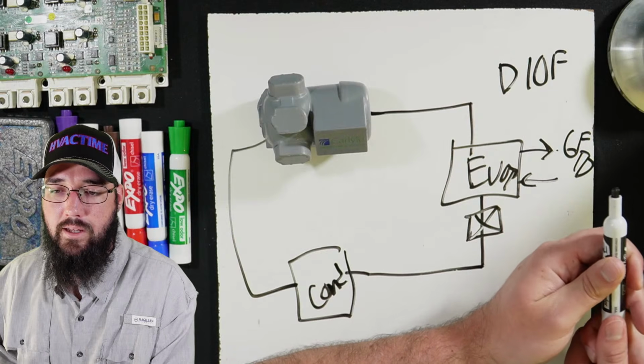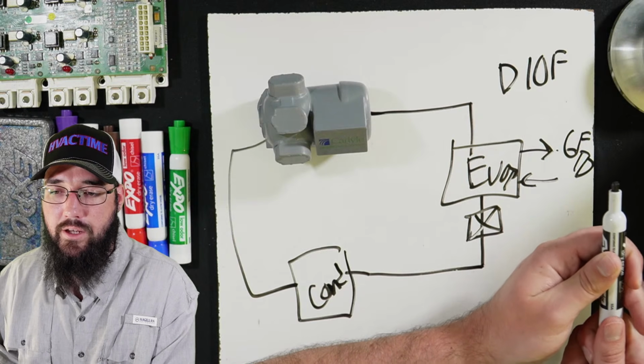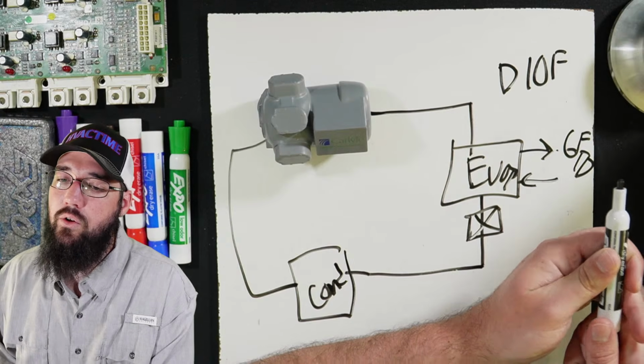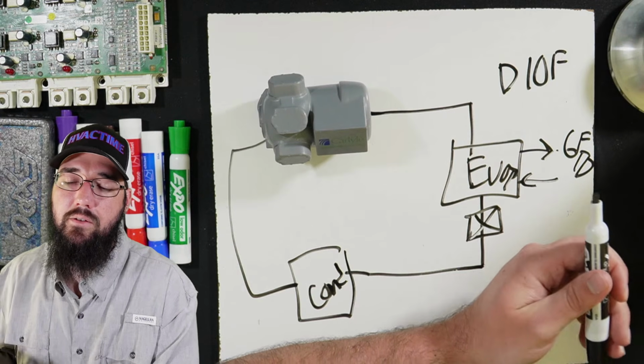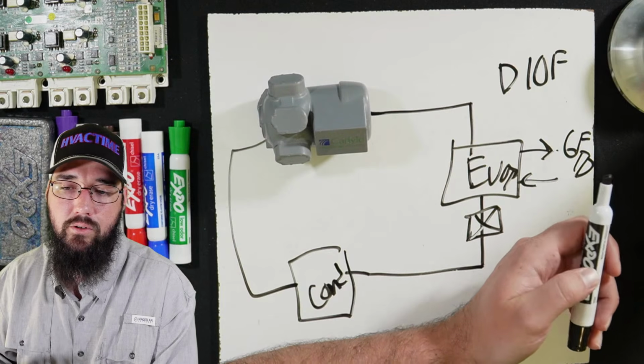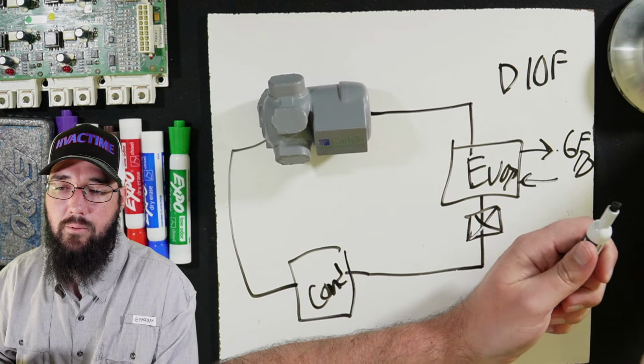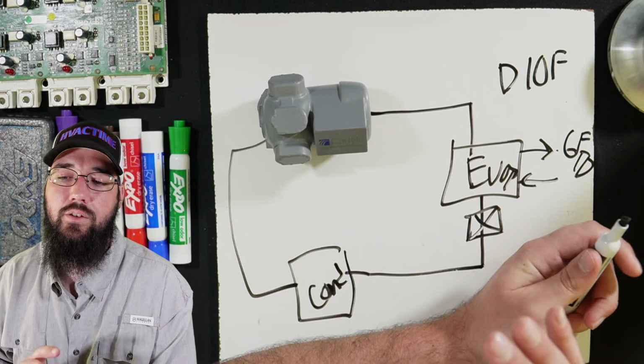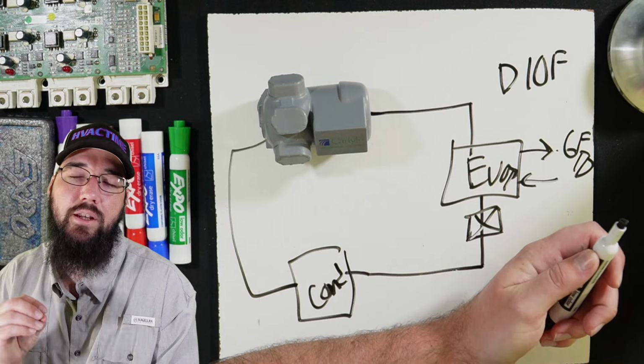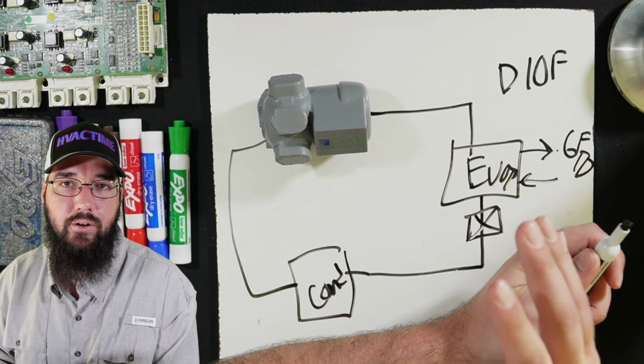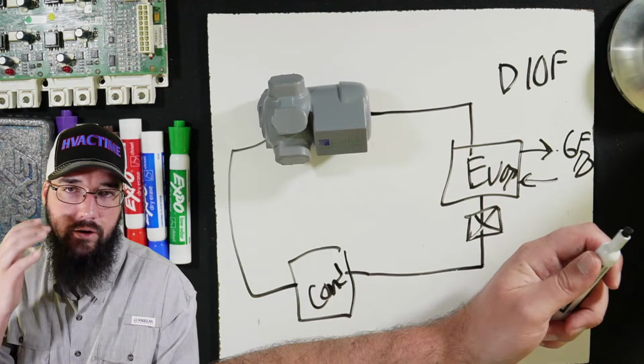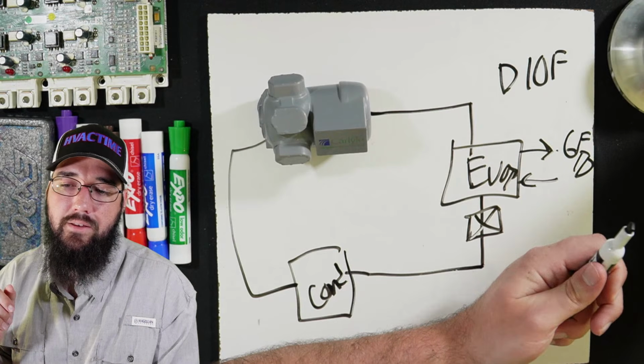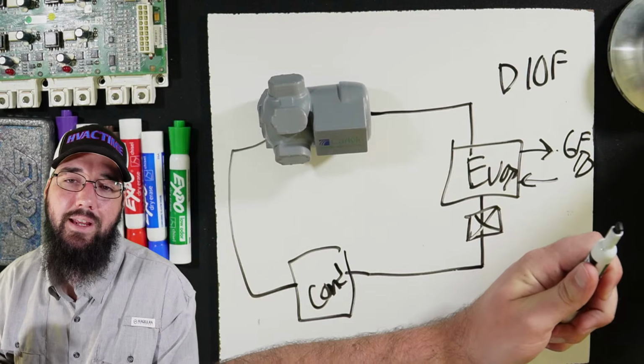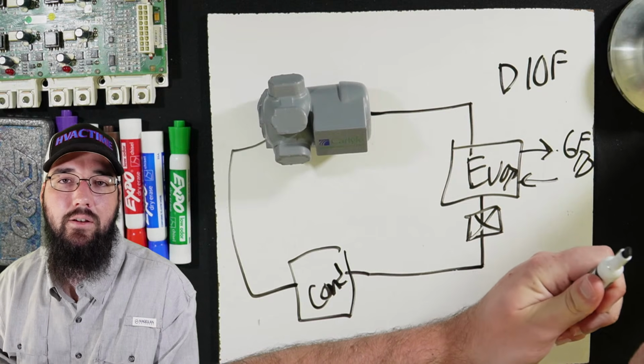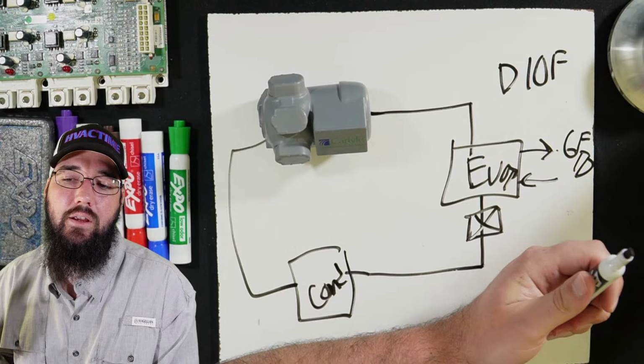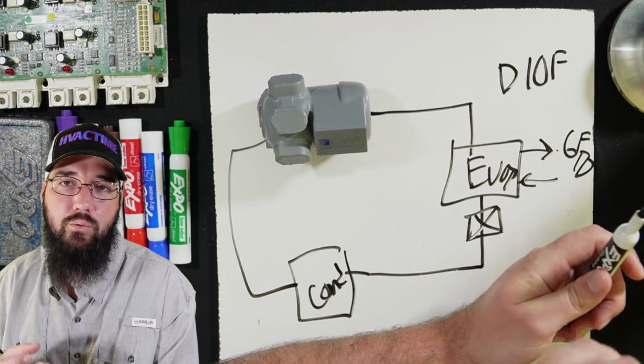So absolutely. Less CFM equals better heat exchange with water. So it's not about the refrigerant itself moving slower. It's not about the refrigerant moving slower, like we would think of it in an air-cooled scenario or an air-over evaporator, like an RTU. It's about the total volume of heat that we need being less. And so the amount of approach required reduces.